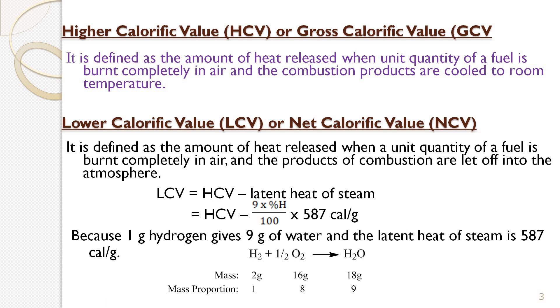Generally, the combustion products are the flue gases and moisture. Moisture is formed due to hydrogen present in the fuel — hydrogen is converted into water vapor, and this water is vaporized by absorbing some amount of heat, which we call the latent heat of steam. In higher calorific value, this latent heat of steam is also included. So the total or gross heat is calculated in this definition, which is why it is called the higher calorific value or gross calorific value.